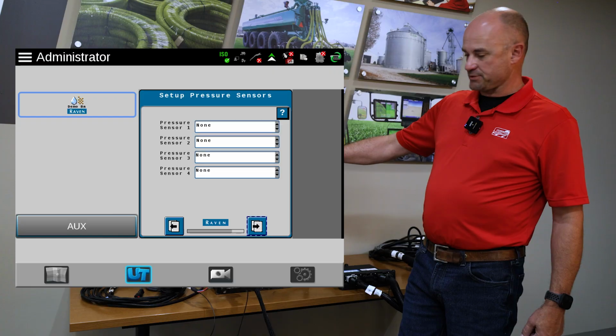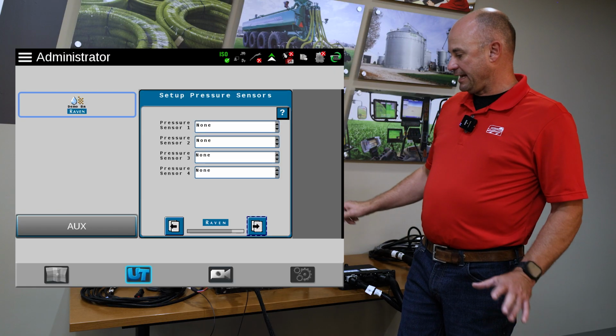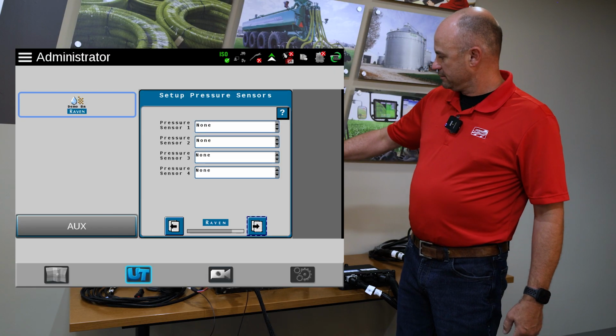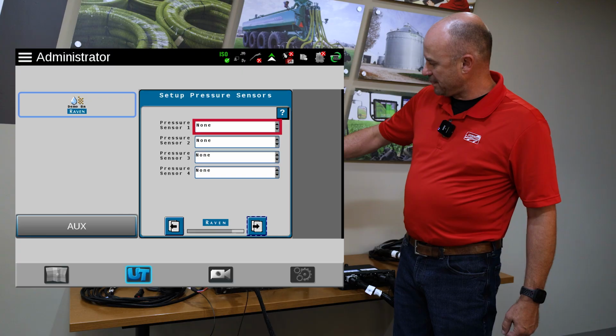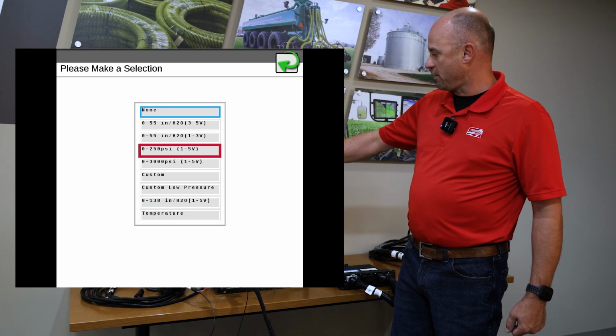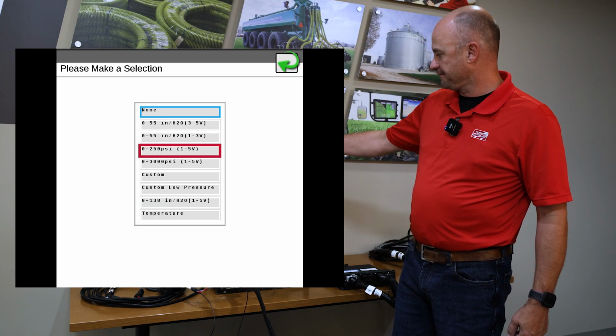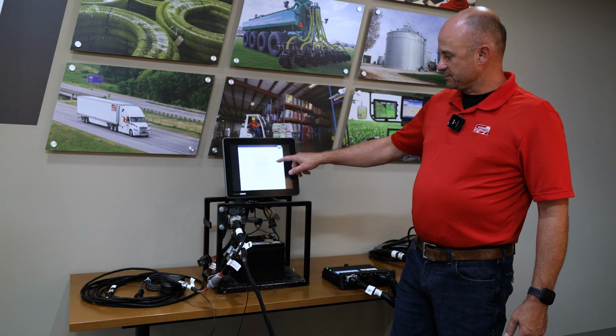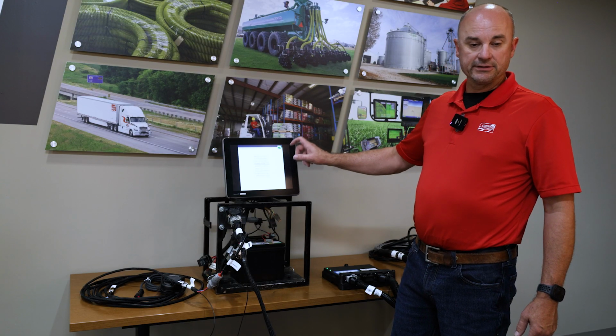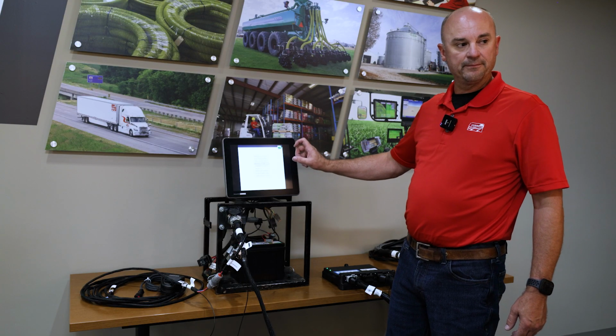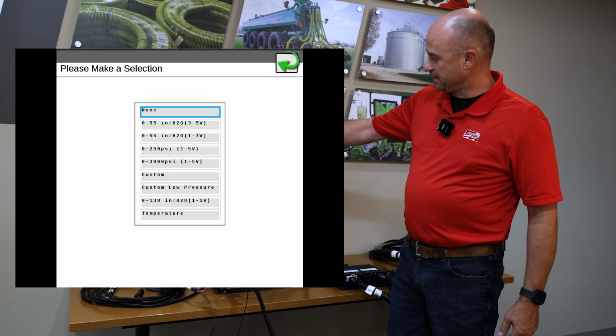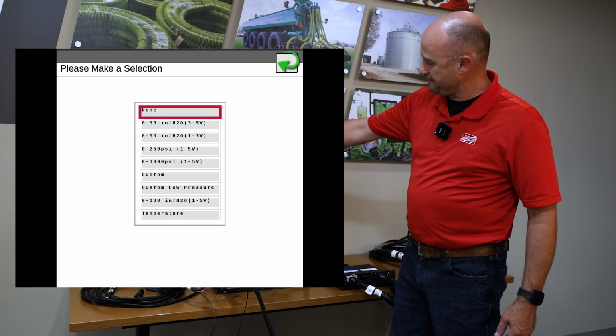Here's where we're going to set our pressure transducers up. I do not have any here right now. If we do, we use the drop-down box - Raven pressure transducers are always 0 to 250 PSI. We select the Raven pressure transducer, and in a later step it will actually confirm that the pressure transducer is hooked up and that it is correct. Because I don't have any, I'm going to hit none right now.